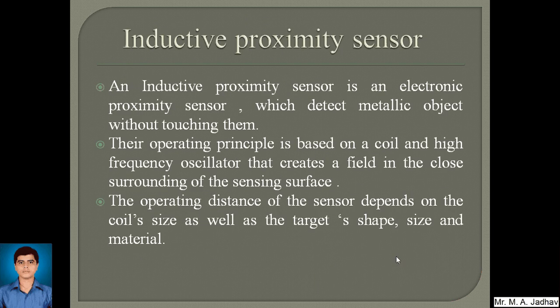First, the inductive proximity sensor. An inductive proximity sensor is an electronic proximity sensor which detects metallic objects without touching them. Its operating principle is based on a coil and a high-frequency oscillator that creates a field in the close surrounding of the sensing surface. The operating distance of the sensor depends on the coil size as well as the target shape, size and material.